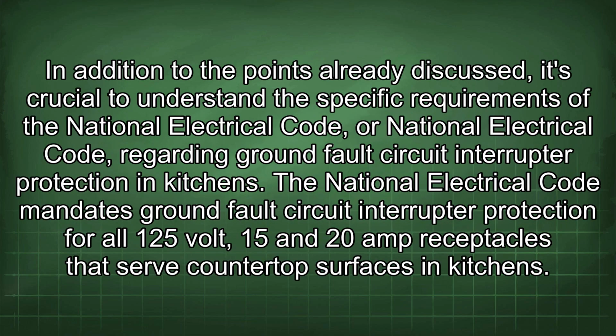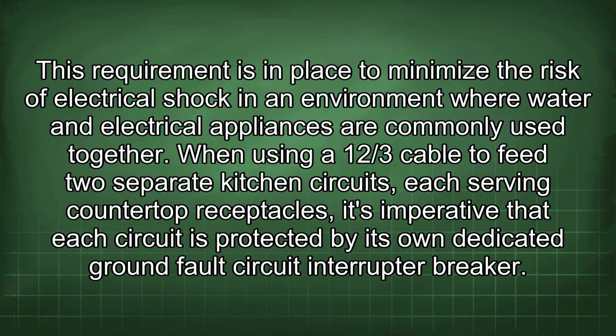In addition to the points already discussed, it's crucial to understand the specific requirements of the National Electrical Code regarding ground fault circuit interrupter protection in kitchens. The National Electrical Code mandates ground fault circuit interrupter protection for all 125-volt, 15 and 20 amp receptacles that serve countertop surfaces in kitchens. This requirement is in place to minimize the risk of electrical shock in an environment where water and electrical appliances are commonly used together.